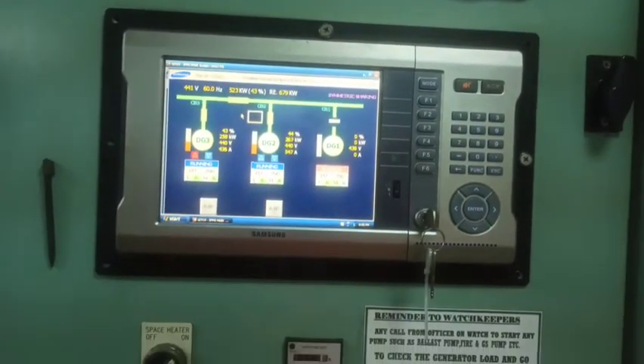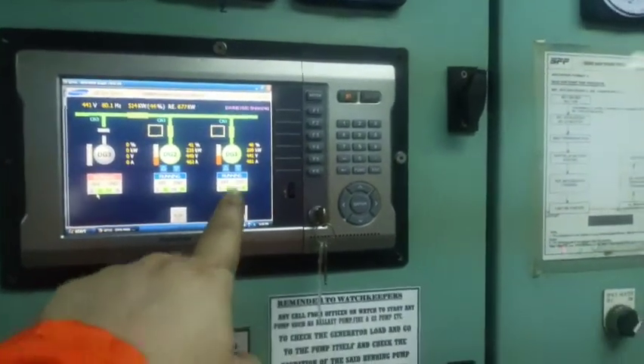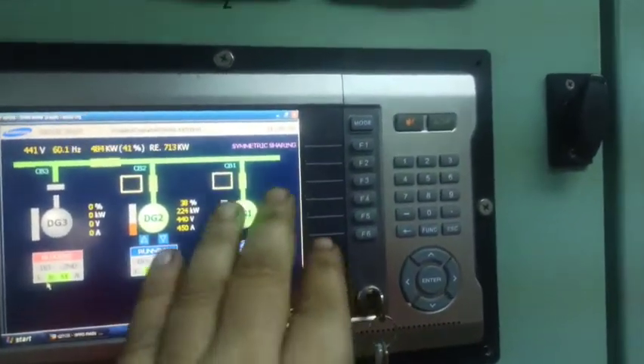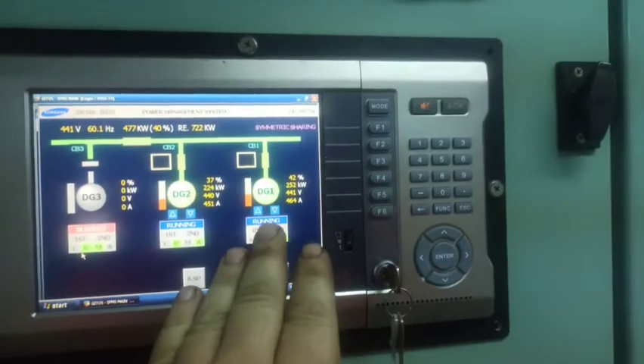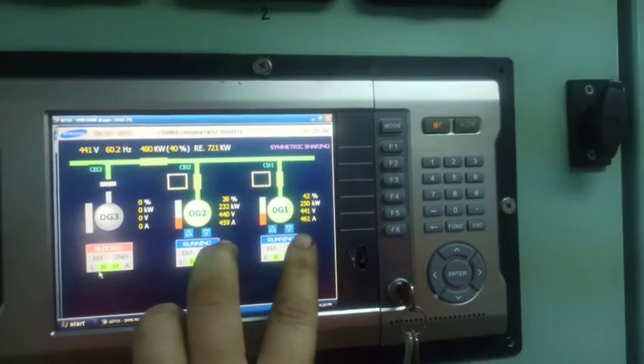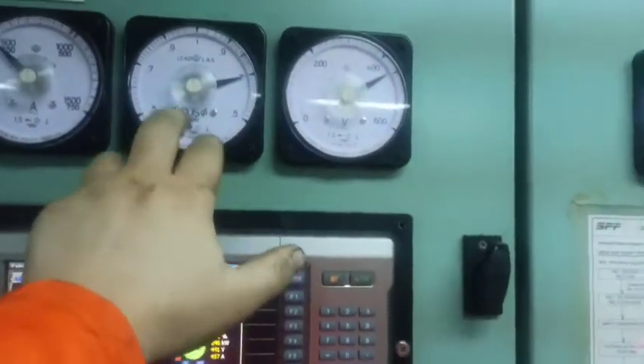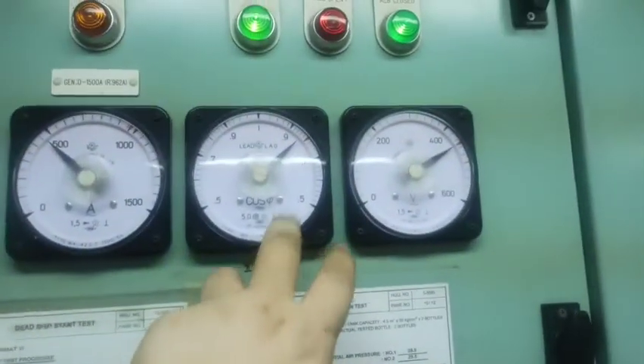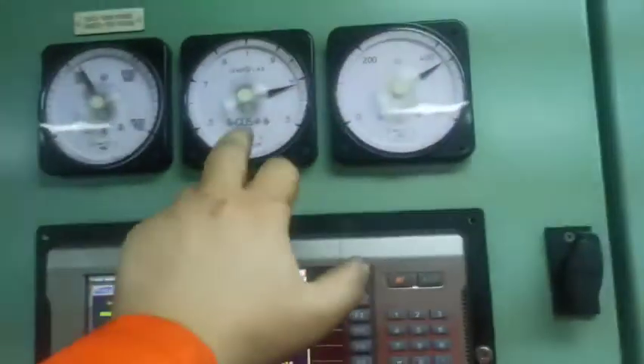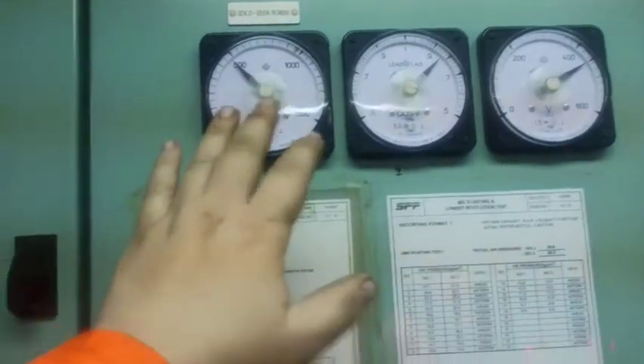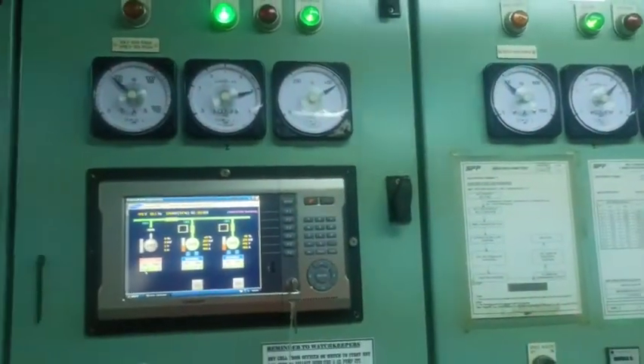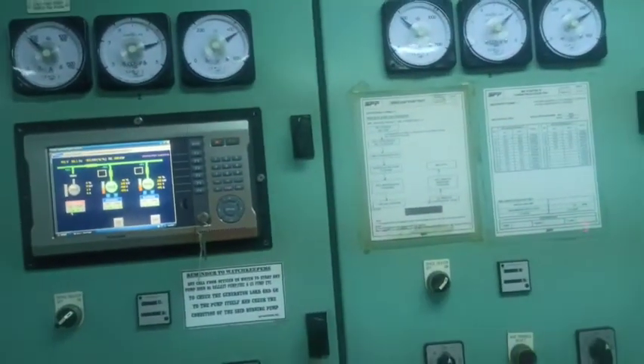Without load. If you make the correct adjustment, after you see when you share the diesel generator we adjust, the AVR must be same. Also the cos phi must be near. But my advice, do not try to adjust the AVR when you have load.